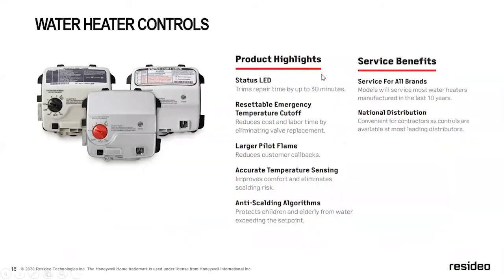So we also have water heater controls, and essentially these are not just gas valves. It's a full control system for your hot water heaters, or gas hot water heaters. The nice thing about these is that they have algorithms built into them that allow them to be anti-scalding, to protect against exceeding any type of the designated set point that you put in it. It has a resettable emergency temperature cutoff, which is really nice. LEDs let you know the status of what's going on with the system.